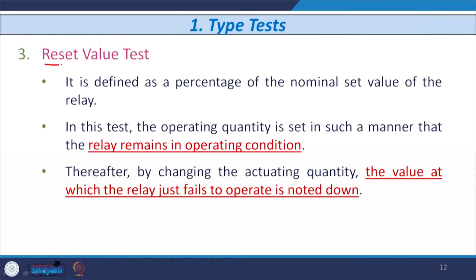The third test is known as the reset value test. This is also one of the type tests to be performed by the manufacturer. It is defined as a percentage of the nominal set value of the relay. Normally in this test, the operating quantity is set in such a manner that the relay always remains in operating condition. Thereafter, by changing the actuating quantity, it can be current, voltage, power, frequency, the value at which the relay just fails to operate is to be noted.